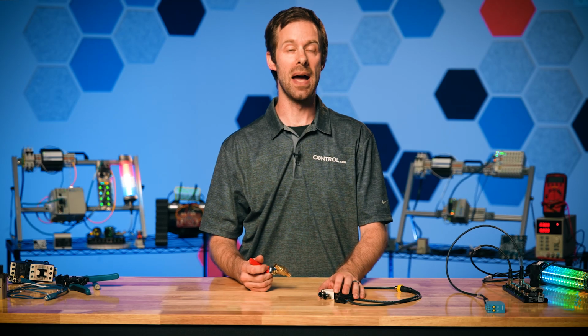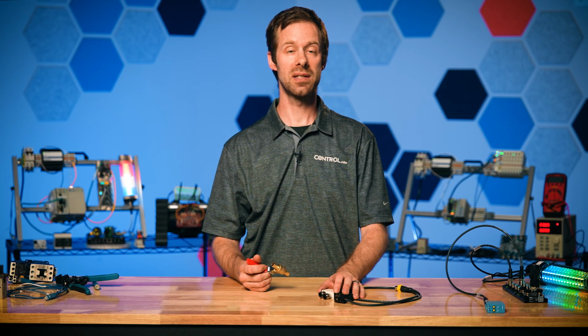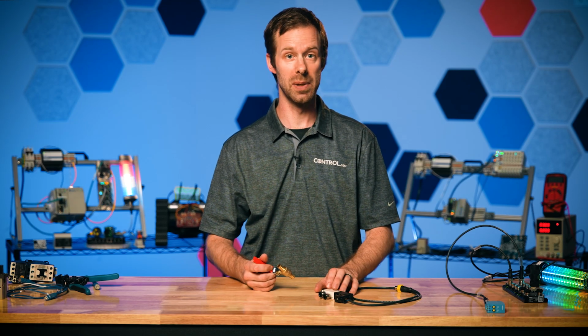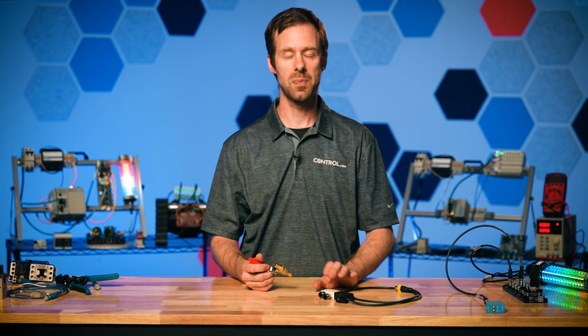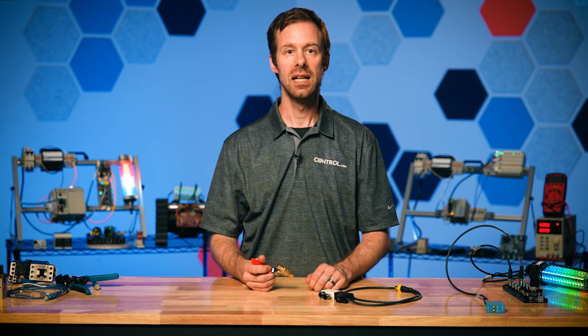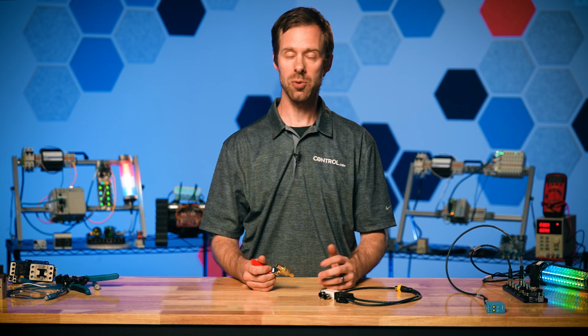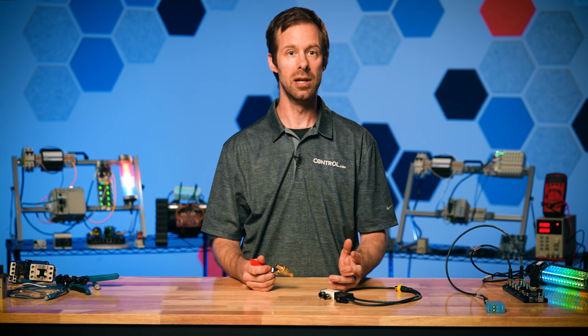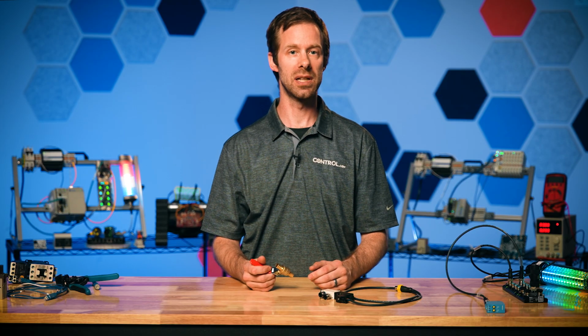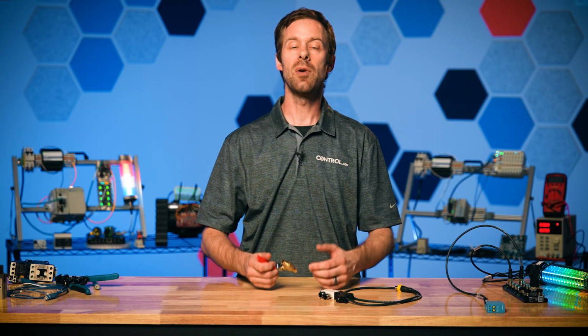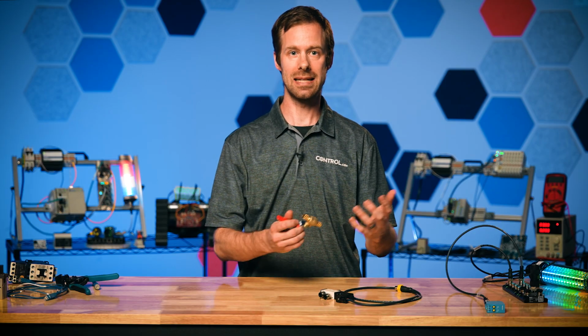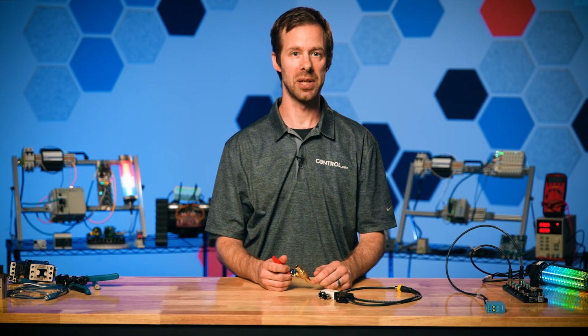When we're dealing with pneumatic systems, pressure losses in all the components are a really big deal that we can't ignore, especially when it comes to valves. There's a few different kinds of valves, but each one is rated in the amount of pressure based on the amount of flow that you can expect to lose, and so you have to account for all of those losses and still have enough pressure to drive the end application.